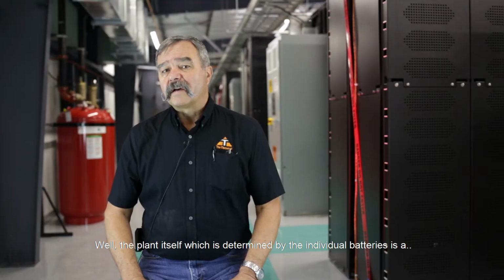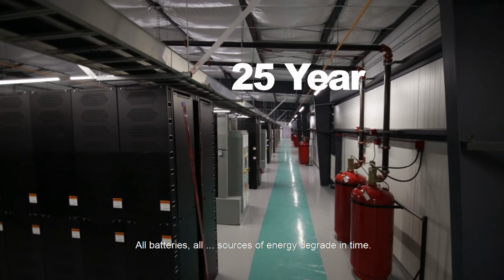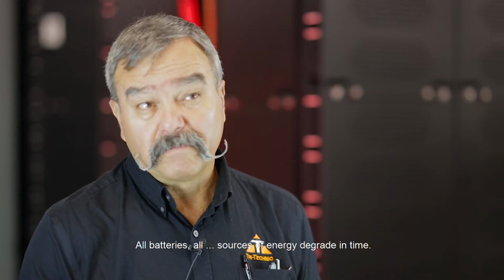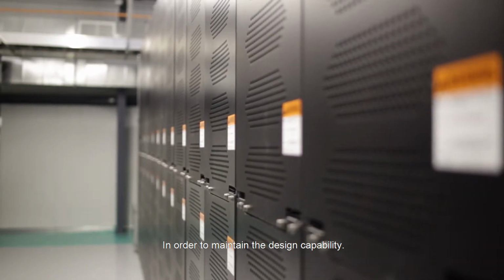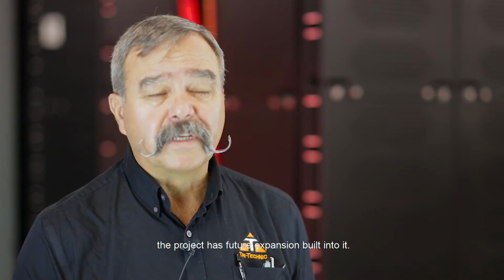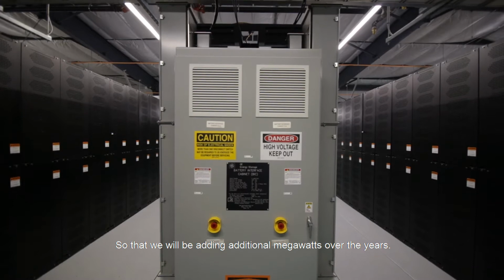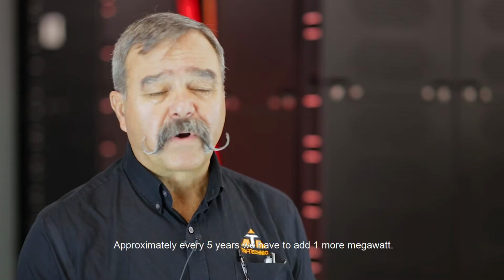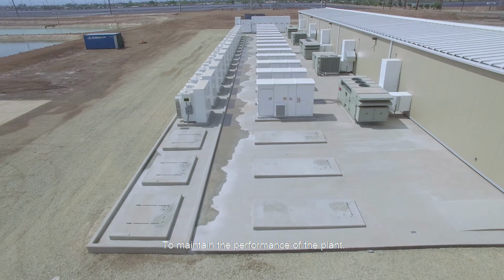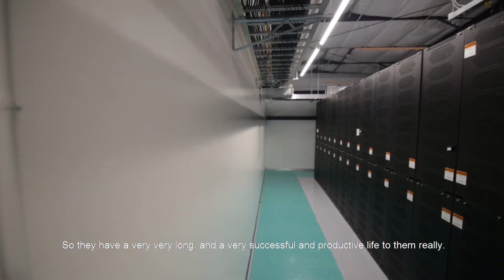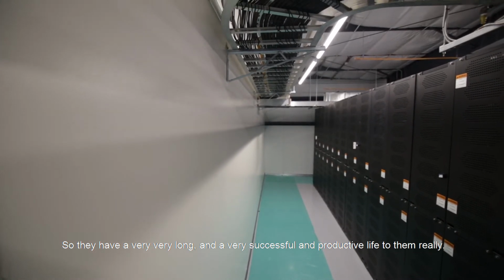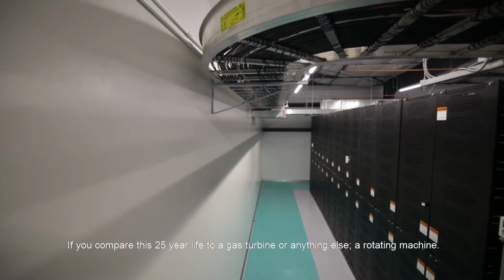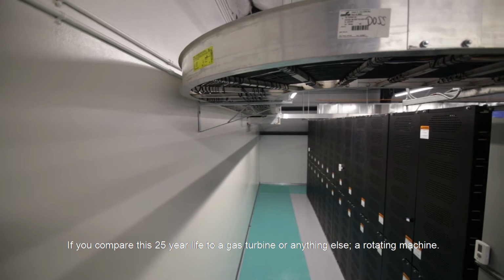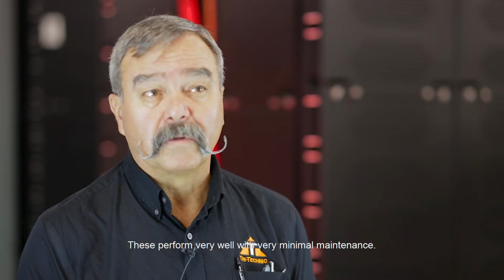The plant itself, determined by the individual batteries, has a 25-year life. All batteries, all sources of energy degrade over time, like lights and everything else. In order to maintain the design capability, this project has future expansion built into it, so we'll be adding additional megawatts over the years, approximately one more megawatt every 5 years to maintain the performance of the plant. So they have a very long and successful, productive life. Compared to a gas turbine or any rotating machine, these perform very well with very minimal maintenance.